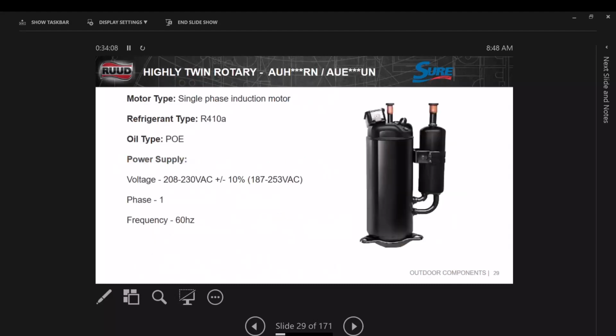A twin rotary compressor is made by Highly. It's been around a long time. They use them in mini splits. Basically, you've seen those. It's a regular PSC compressor. It's not a typical three-phase type compressor you're going to see in variable speed. Right? It has POE oil in it. It's R410A, 208, 230 volt, plus or minus 10%. It's single phase, and the frequency is 60 hertz.